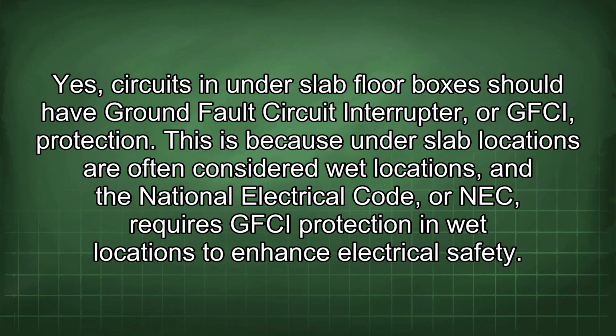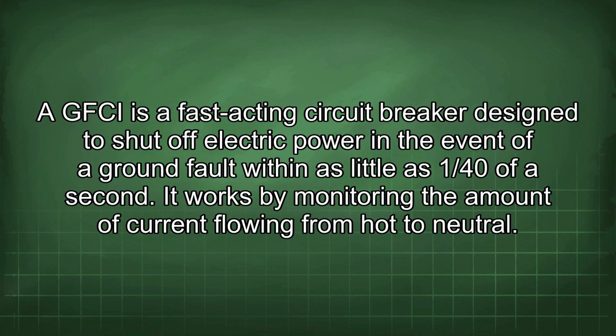Yes, circuits in under-slab floor boxes should have ground fault circuit interrupter, or GFCI, protection. This is because under-slab locations are often considered wet locations, and the National Electrical Code, or NEC, requires GFCI protection in wet locations to enhance electrical safety. A GFCI is a fast-acting circuit breaker designed to shut off electric power in the event of a ground fault within as little as 1/40 of a second.